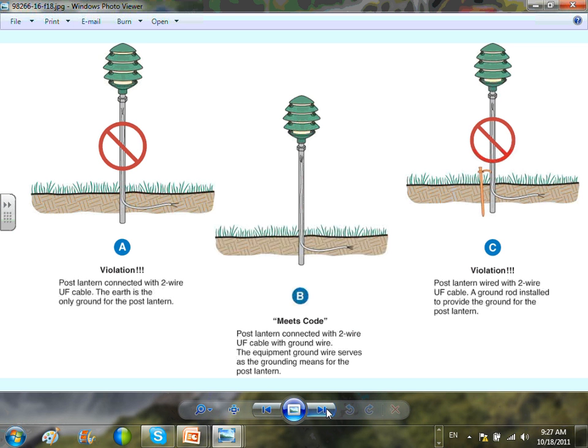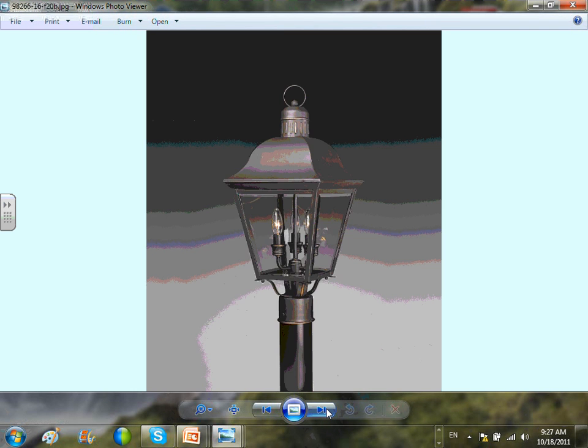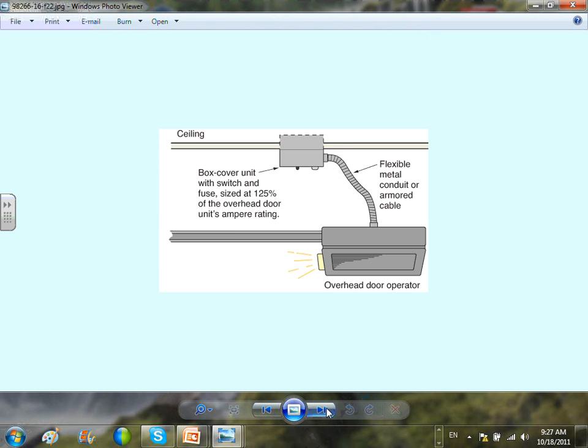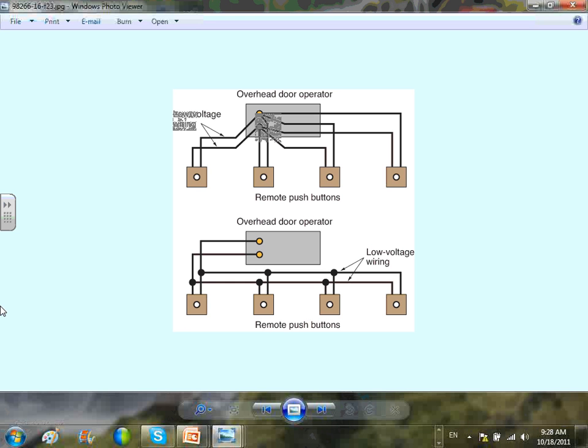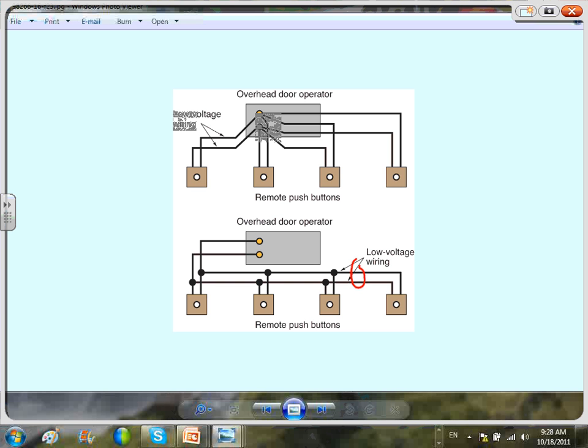Okay, conduit, protecting. Talk about the ground. Garage door opener. This is just a low voltage picture, guys, of how the garage door opener works. They use 18/2 or something like that cable, something similar to that wire. Can you guys see that these are push buttons where you can open your garage from multiple locations? For your garage door opener, overhead operator, you can wire all of them in parallel. When you push it, you energize the coil over here, and the coil closes the magnetic starter and allows the garage door to open and close.